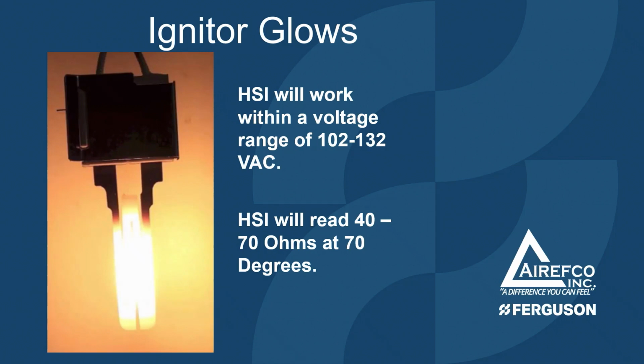Next, the igniter will glow. The hot surface igniter will work within a voltage range of 102 to 132 volts AC. When the HSI is in good shape, it will read between 40 and 70 ohms at 70 degrees.